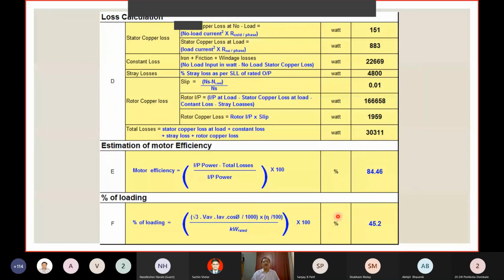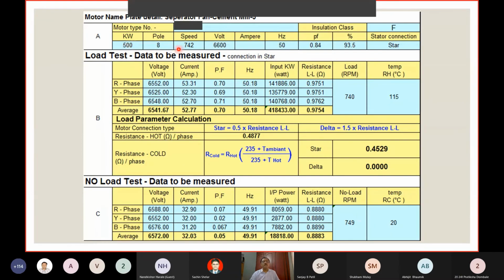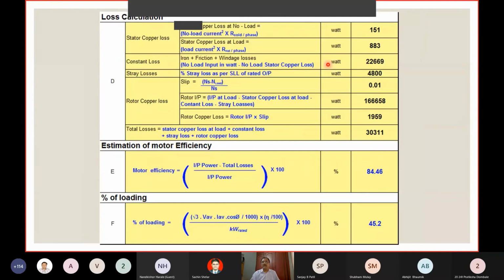This is one skill we have where we are able to segregate all the losses, sum it up, and arrive at the motor efficiency as well as the load factor. So this motor, which is 500 kilowatt, 8 pole, 6.6 kV, whose nameplate efficiency is 93.5%, at 45% load, and also due to aging, has reduced to 84.5% efficiency. So this motor is definitely a good opportunity, because today new motors TFC are available with 95 to 97% efficiency. So this is a requirement which came up from a cement plant. Customer has replaced this motor and has also reported energy saving.